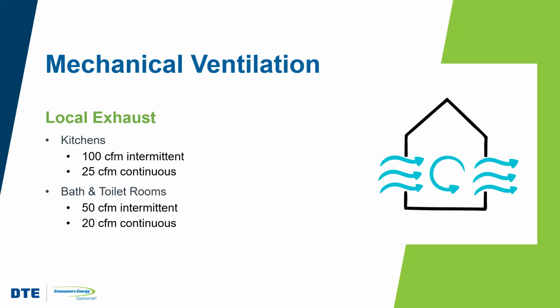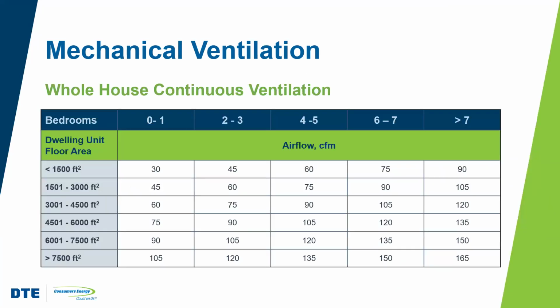For example, local kitchen exhaust that operates 24/7 would be at a low ventilation rate of 25 cubic feet per minute. But if the range hood fan were only to operate when cooking is taking place, then the airflow rate would need to be higher, 100 cubic feet per minute. But again, only when operating.